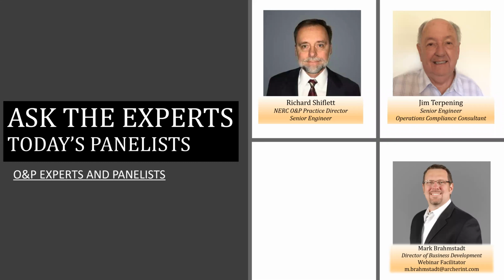The short answer is yes. Unfortunately, even though in this situation it sounds like the GO only owns a little bit beyond this GSU transformer - there was a breaker on the high side of the GSU - if you recall, R2 begins at the point at the GSU, whether high side or low side depending on who owns the GSU, out to the TO's demarcation point. If that's just a few components out, the GO owns those few components, maybe including the breaker just referenced in the question.